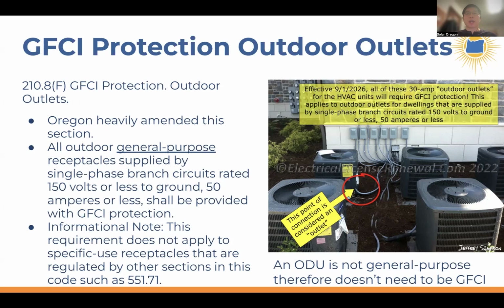When that idea first came into play, not even in the 2023 electric code cycle but the 2020 cycle, experiments found that the startup of air conditioners and heat pumps creates transient voltage electrical behaviors that result in tripping the GFCI. These nuisance trips happen because the electric industry hasn't yet produced a GFCI that can distinguish a real ground fault from these transient electrical signatures coming out of the outdoor unit.